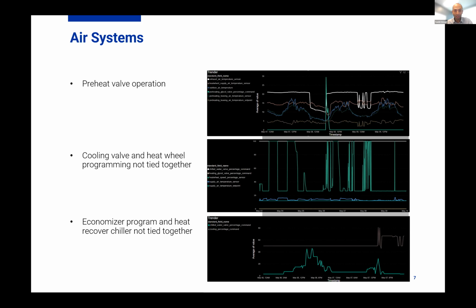We have a heat recovery chiller in this building, and what we have is a sequence just to create load and extract as much heat as possible. But our cooling valve operation wasn't set up to work properly with our heat wheels. During the testing, because it was done in wintertime, no one really looked at the cooling valve operation, and we found out that instead of modulating our heat wheels and getting as much heat transfer as possible, we were opening our cooling valves 100% of the time. We're not even achieving any energy savings from our heat recovery chiller because the sequence isn't properly optimized in between.